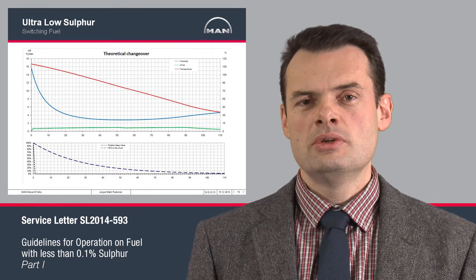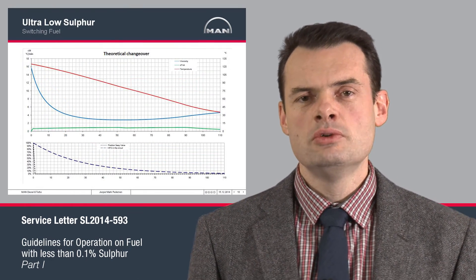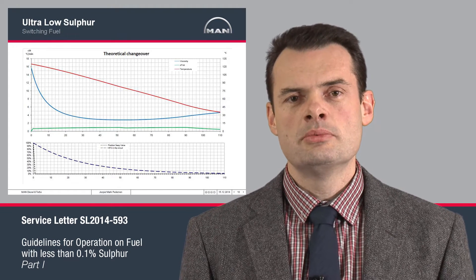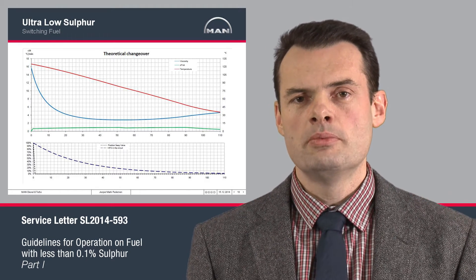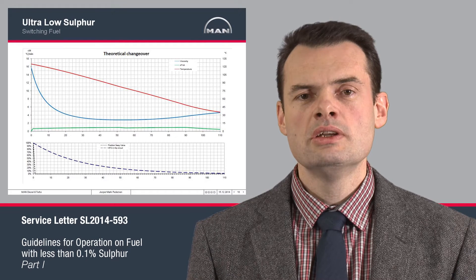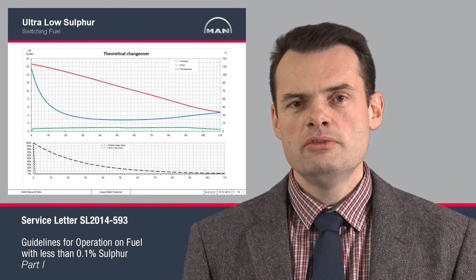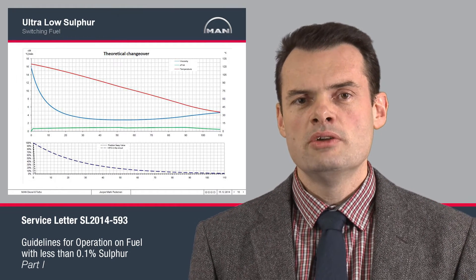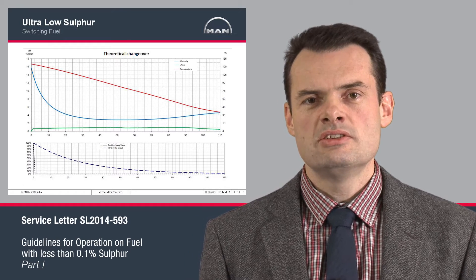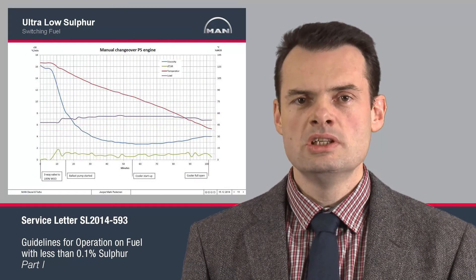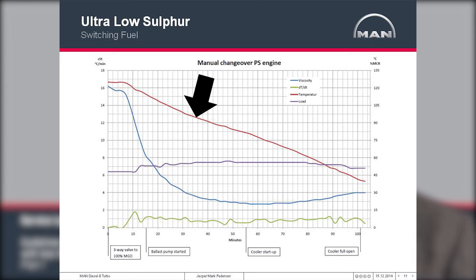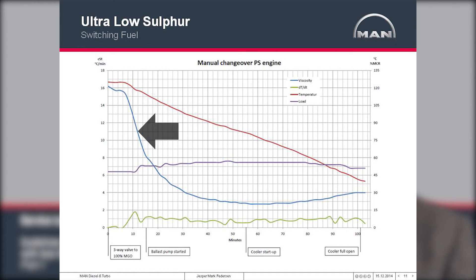A practical example is shown here from a switch from heavy fuel to distillates under steady operation. The engine was operating at 50% engine load and we switched the valve to distillates and followed the viscosity as the change happened. The temperature decreased by approximately one degree per minute, a little bit lower than our recommendation. We do allow two degrees per minute for change, but as you can see, with the given engine load, the viscosity dropped very rapidly.